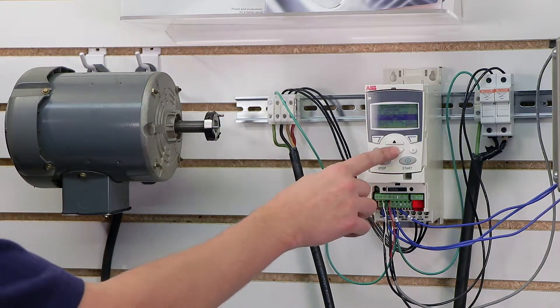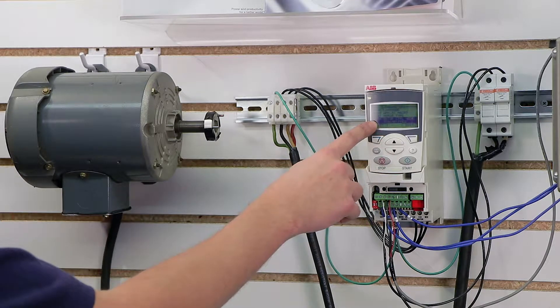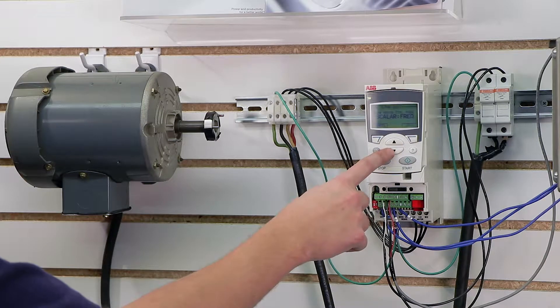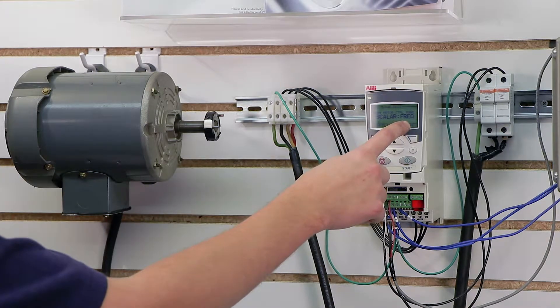Then I'm going to go down to 9904, and this is where we're going to select our tuning type. I'm going to click edit, and we have scalar frequency, which basically means we're going to do standard volts per hertz without tuning. But I'm going to go down to vector.